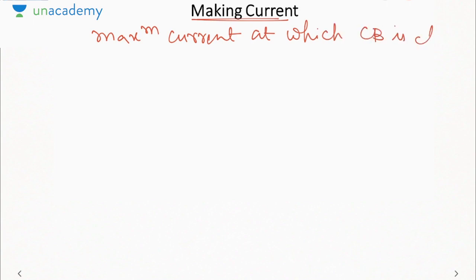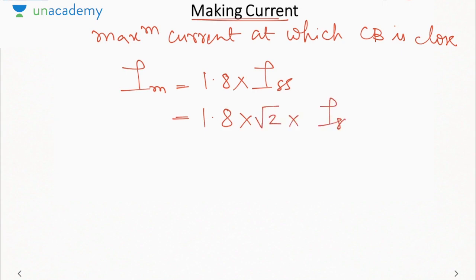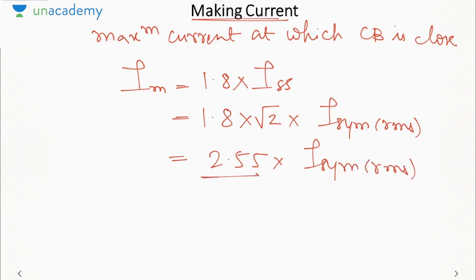Similarly, the next current is called the making current. It is the maximum current at which the circuit breaker is closed. As I told you, the circuit breaker always operates in the transient region and not in the subtransient. So for high subtransient current, the circuit breaker contacts will remain closed. So if the circuit breaker contacts remain closed, we will say that Im will be 1.8 times I steady state. In the fault analysis we derived a factor of 2, but practically this factor is less than 2, so we are considering 1.8. So 1.8 into root 2 into I symmetrical RMS will be 2.55 times I symmetrical RMS. So that is your making current.